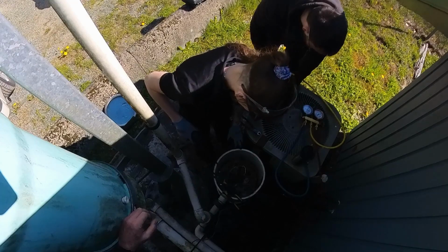So before we replaced the condensing unit there, we did another very extensive leak test on the heat exchanger. And here's the crazy thing. We checked that heat exchanger for a refrigerant leak several times, more than 3 or 4 times, just because we were like, hey, we just want to check this again. We're just going to check this again. So we checked it several times. The one time we did check, after all of these pressure tests and everything, we detected a leak. Our leak detector was screaming. It detected a leak. Okay, let's see what 300 does.